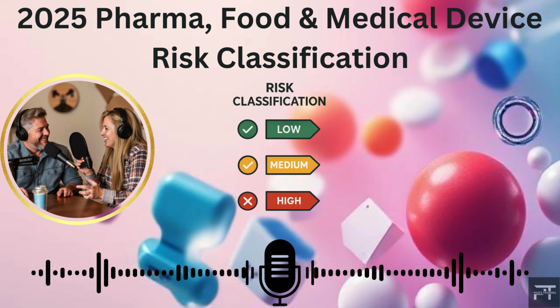All right, let's tackle our last category here, medical devices. How do we classify those based on their level of risk? Okay, so medical devices are classified based on a few key things: how they're meant to be used, how invasive they are, or how much they interact with the patient's body, and the general risks associated with their use. There's been a real push to harmonize these classifications globally through organizations like the FDA, the European Medical Devices Regulation, the EU MDR, and the ISO 13485 standard.